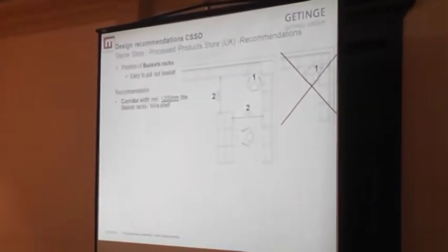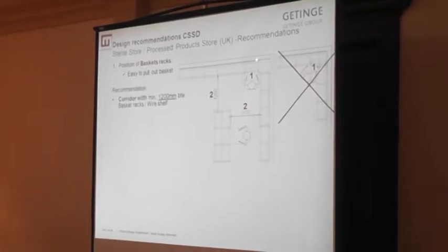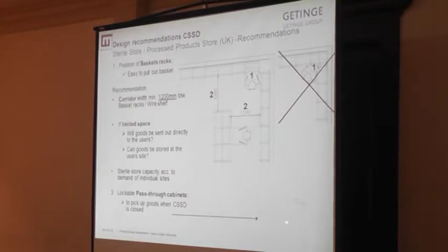Then in the sterile store, the recommended distance is 1200 millimeters between the basket racks so we can work properly with the baskets. We cannot put the basket racks side by side, because then we cannot enter like that. There must be some gap here. And if we have limited space, we can send it more frequently to the customers, as we discussed. And we can have lockable pass-through cabinets if we have night time, and we can lock it if we have a problem with someone taking the items. We can have some kind of storage here, and you can have a key for that.